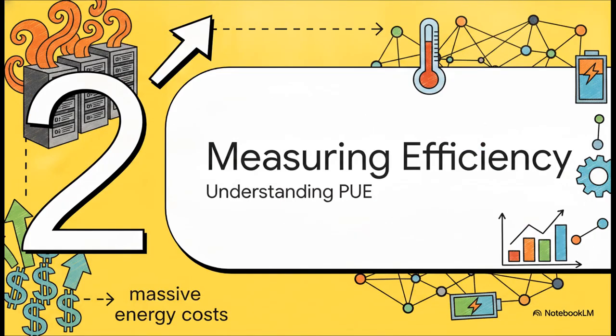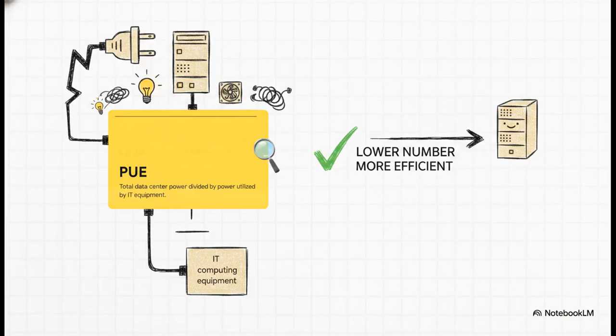Which brings us to Section 2, measuring efficiency with PUE. So, knowing that heat is our biggest enemy here, how does the industry quantify these costs? Well, the gold standard metric is PUE, which stands for Power Usage Effectiveness. It's a simple ratio. You take the total power entering the facility and divide it by the power actually being used by the IT equipment. Since that facility power includes all the overhead, like that massive cooling we just talked about, the ratio is always going to be greater than 1. The key takeaway? A lower number means a much more efficient data center.